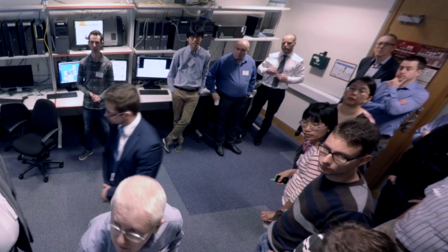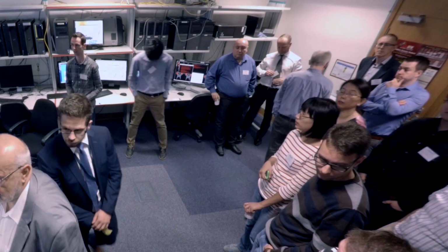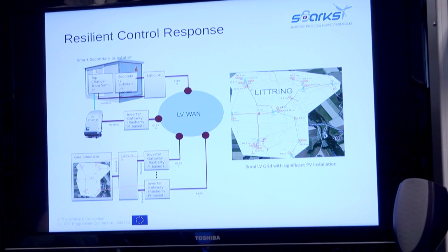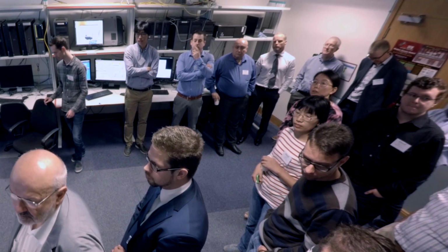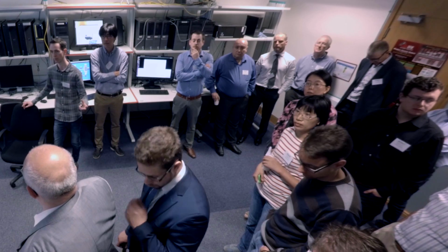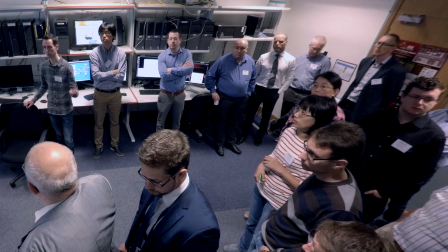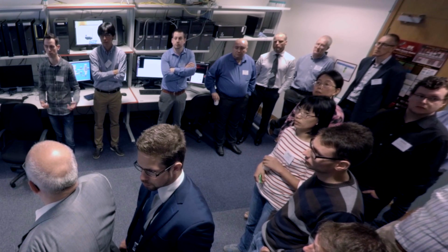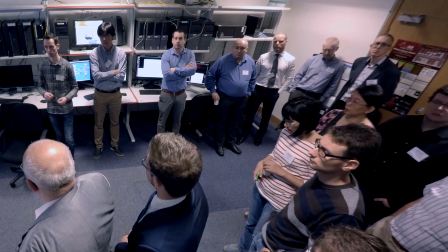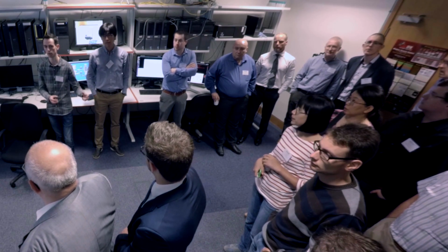So the question is, so what? What we want to do is move beyond just generating intrusion detection alerts that appear at an operator who just goes, well, that went wrong. We want to move to a system that can be more resilient and take action whenever these alerts are generated. So in another part of the project, KTH, the university, are developing resilient control. This means that if it gets some information that the underlying system may be under attack, it takes some action in the control itself to try and mitigate that, possibly ignore the information it's getting from the network, and put the system back into a default state, which you know is safe.